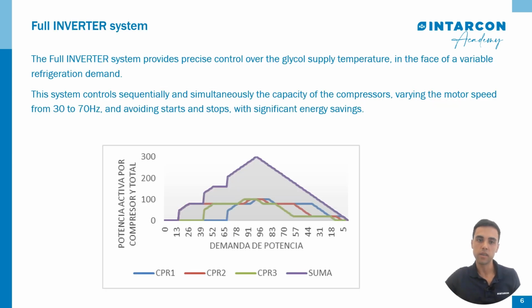The inverter system provides precise control over the glycol supply temperature in the face of a variable refrigeration demand. In this photo, we can see the compressor use for a cooling capacity demand that the control modules manage sequentially and simultaneously and also proportionally thanks to the VFD, avoiding starts and stops with significant energy savings.